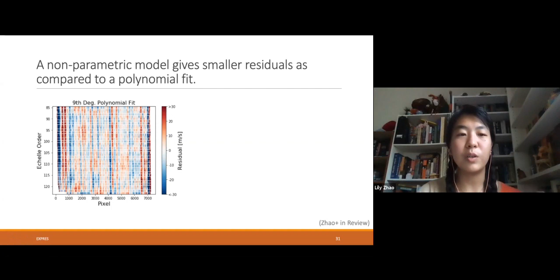And so here we have the lines plotted as typically by pixel position and order, and then colored by the difference between the predicted wavelengths and the assigned wavelengths. And so while small, you can see all of this structure there, these patches and these horizontal stripes that are showing up in the polynomial fit residuals. But if we use a non-parametric model instead, you get a much smoother set of residuals, no features, and they're all on average a lot smaller.